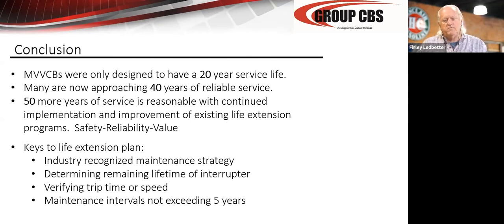If you've got a hot rod or a motorcycle, you can tell there's a problem with it. If you think you hear something, put a spare in it, send that one out to a qualified shop and find out what the issue is. It's not worth a failure, because a catastrophic failure can not only take that circuit, it can take the two circuits beside it with it. That's three sections of switchgear down. That's at the minimum 4, 5, 6 days of outage.